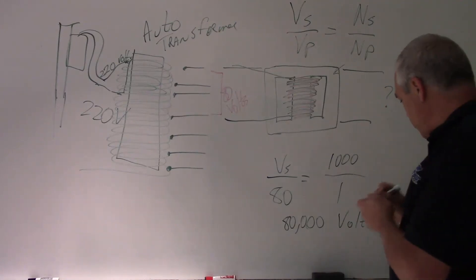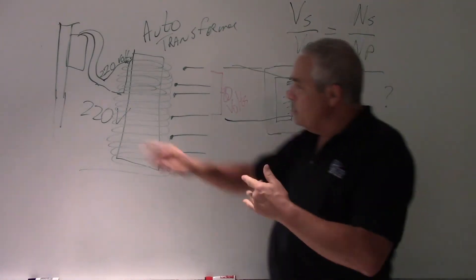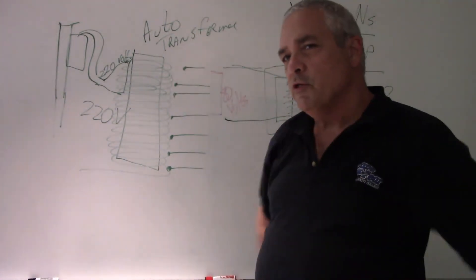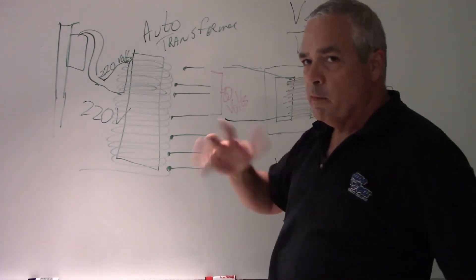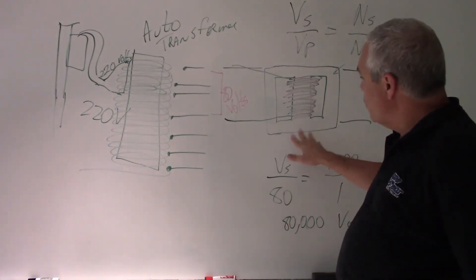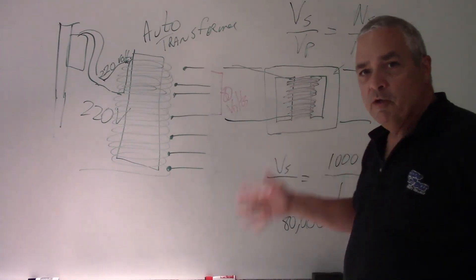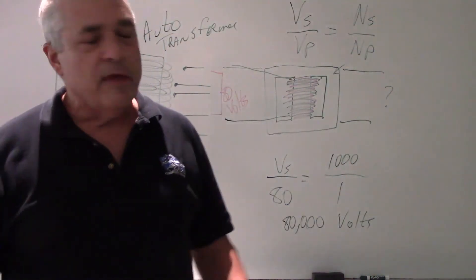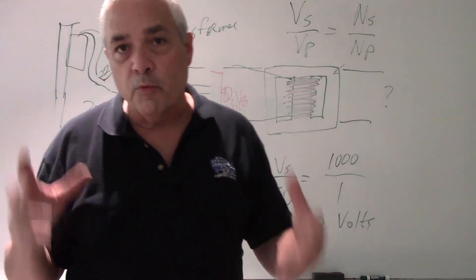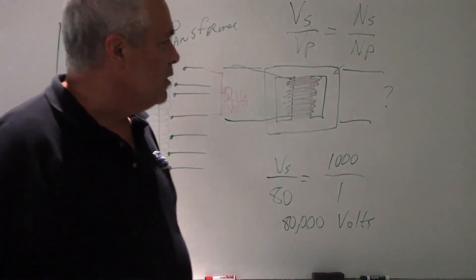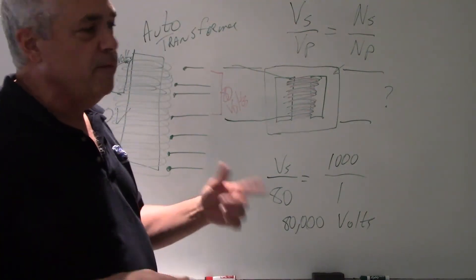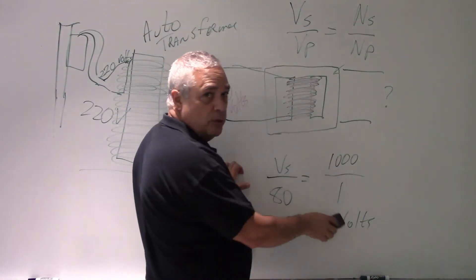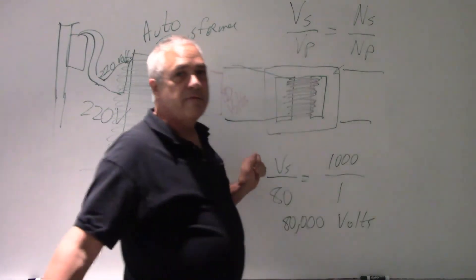Now, as you know, coming in from the street we were using alternating current. Going into the auto transformer and into the primary high voltage transformer — also alternating current, because transformers only work with alternating current. But didn't we say in a previous video that for X-ray production, the tube needs to be rigged up to direct current? Yes, absolutely right. So we have another step to go through: we need to feed those 80,000 volts through a rectification circuit.